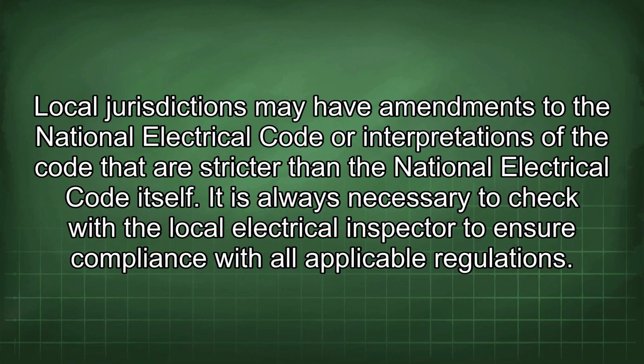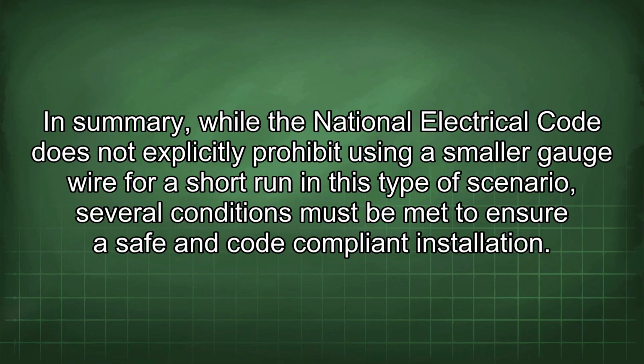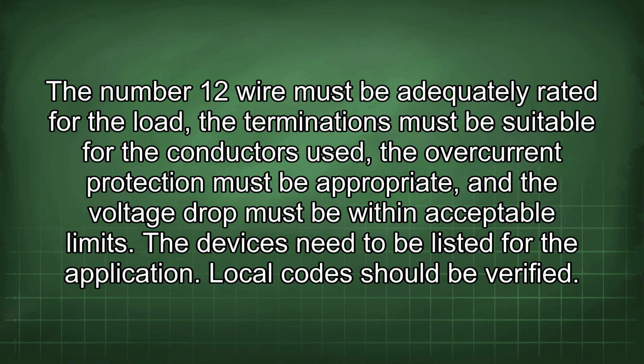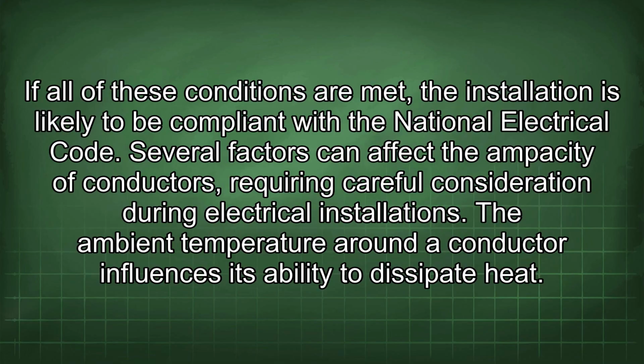In summary, while the National Electrical Code does not explicitly prohibit using a smaller gauge wire for a short run in this type of scenario, several conditions must be met to ensure a safe and code-compliant installation. The number 12 wire must be adequately rated for the load, the terminations must be suitable for the conductors used, the overcurrent protection must be appropriate, and the voltage drop must be within acceptable limits. The devices need to be listed for the application. Local codes should be verified. If all of these conditions are met, the installation is likely to be compliant with the National Electrical Code.